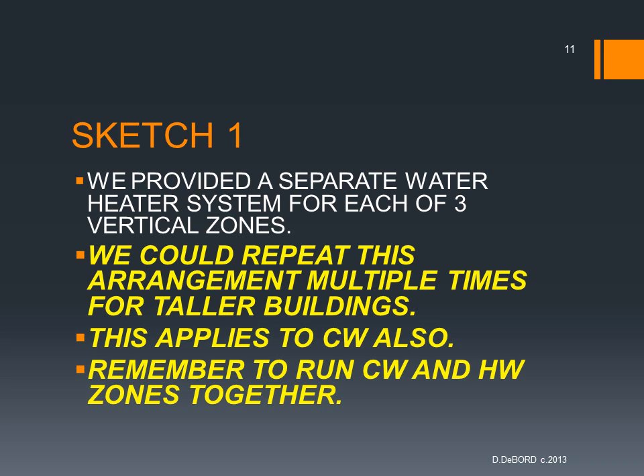Now this applies to cold water also. And remember to run the cold water and hot water zones together. We can have downfeed and upfeed in the same systems, but for every zone, if the cold water downfeeds, the hot water downfeeds, and vice versa. Don't mix them. Don't have cold water upfeeding and hot water downfeeding. Theoretically, the pressures balance, but in real life scenarios, it doesn't work exactly like that, and you can have balancing problems. There are more things that can go wrong to cause some anomalies and have your pressure balancing off. Could play havoc with your mixing valves.